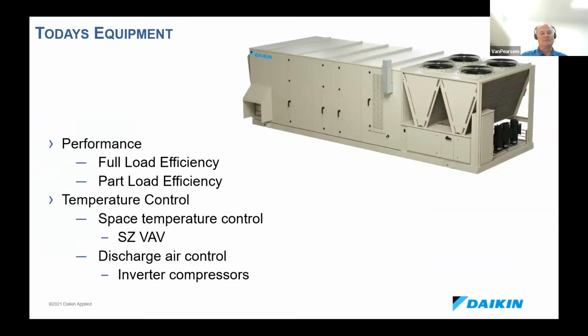So what has happened with today's equipment? The 90.1 energy code has a high effect on the equipment, in which the full load efficiencies have been constantly increasing. The gravitation away from full load efficiency to part load efficiency, the IEERs of equipment, has been the big push. Doing all of that takes more and more technology. The energy code also requires single zone VAV applications all the way down to 6 and 5 ton units, in which fan speeds have to be modulating. It isn't constant volume anymore, and all of that requires technology.